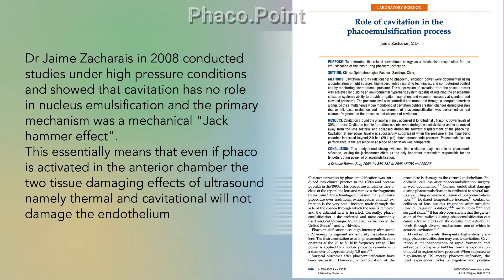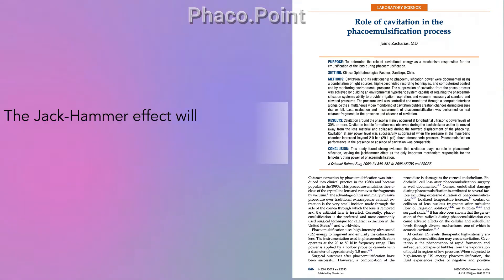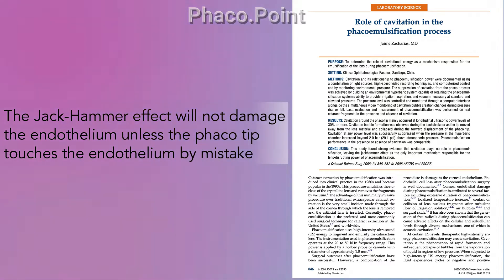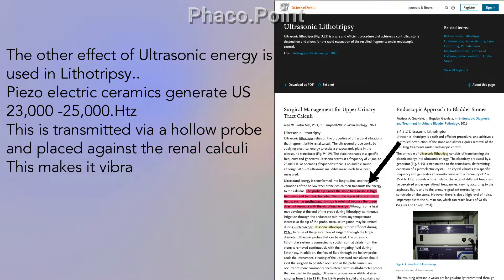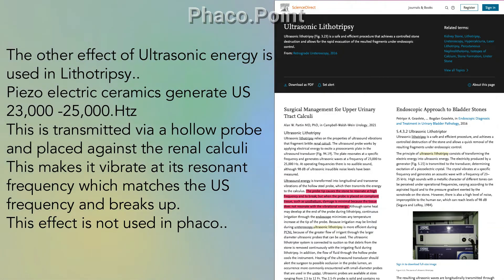This essentially means that even if phaco is activated in the anterior chamber, the two tissue-damaging effects of ultrasound — thermal and cavitational — will not damage the endothelium. The jackhammer effect also will not damage the endothelium unless the phaco tip touches the endothelium directly by mistake. The vibratory effect of ultrasonic energy is used in lithotripsy, where piezoelectric ceramics generate 23,000 to 25,000 hertz, transmitted by a hollow probe placed against renal calculi, making them vibrate at their resonant frequency and break up.